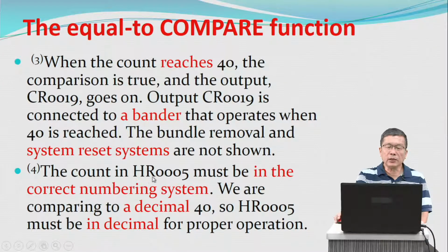The count in holding register number 5 must be in the correct numbering system. We are comparing to a decimal 40, so holding register number 5 must be in decimal for proper operation.